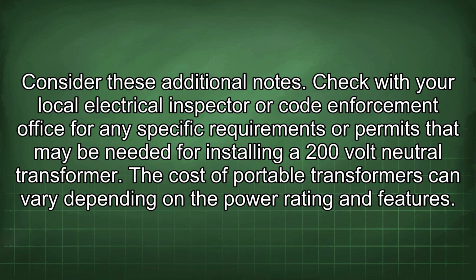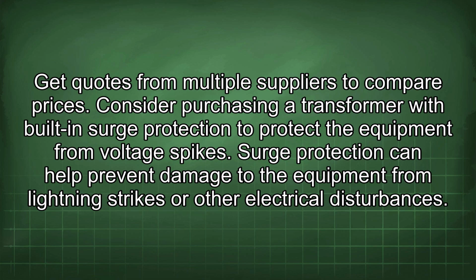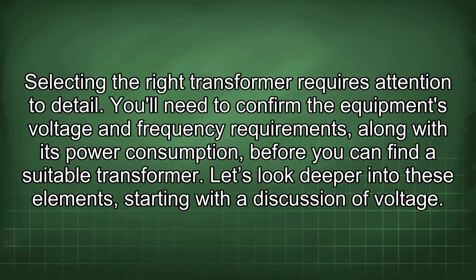The cost of portable transformers can vary depending on the power rating and features. Get quotes from multiple suppliers to compare prices. Consider purchasing a transformer with built-in surge protection to protect the equipment from voltage spikes. Surge protection can help prevent damage to the equipment from lightning strikes or other electrical disturbances. Selecting the right transformer requires attention to detail. You'll need to confirm the equipment's voltage and frequency requirements along with its power consumption before you can find a suitable transformer. Let's look deeper into these elements, starting with a discussion of voltage.